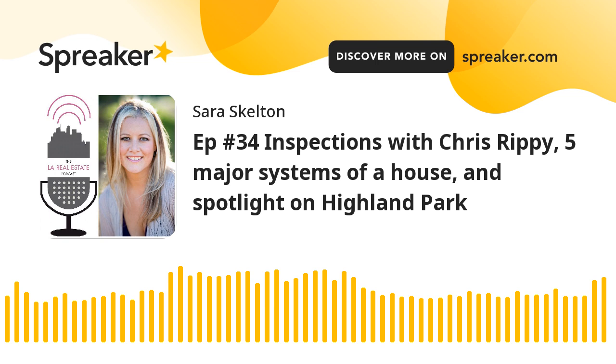Copper's been around for an awful long time, but of course, keep in mind there are different grades of copper. You talk to a good qualified certified plumber, and they have their own ideas on what is acceptable and what isn't. Typically there are 3 grades of copper that we have access to here in California, and there are really only 2 that most qualified plumbers will commit to using. One of them is a much softer, much thinner material and not commonly used, but unfortunately we do find it used, especially in our flipped homes. And that's something that as an inspector, we want to identify and present to the client.